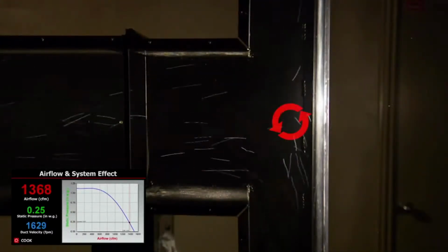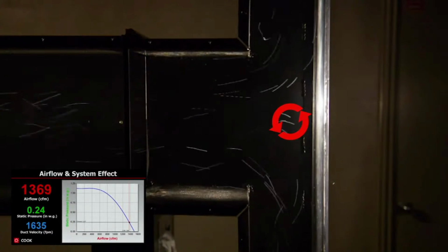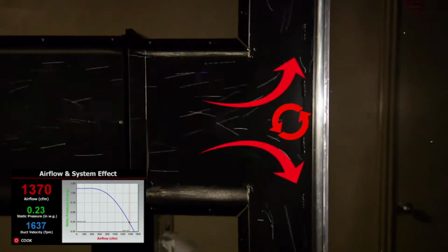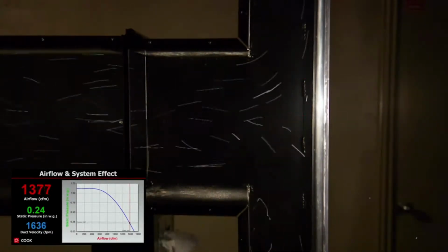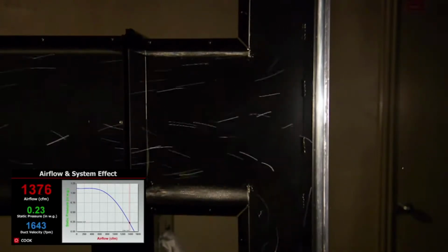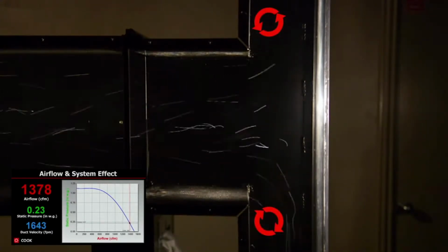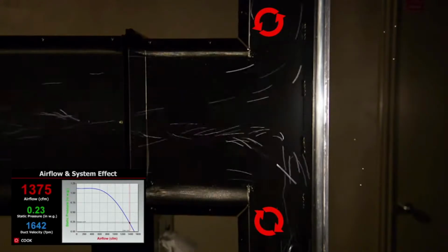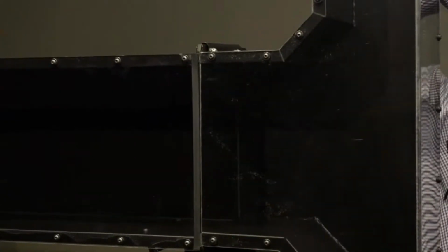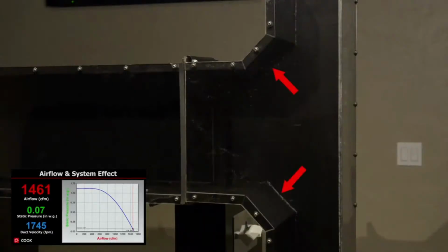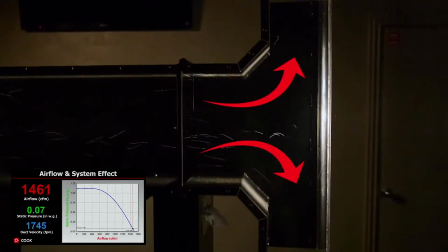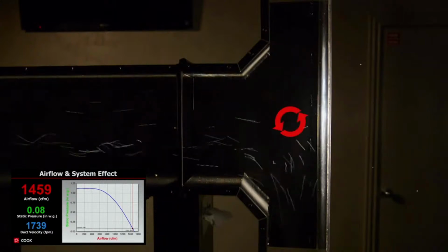Looking closer, we find that a small dam of air formed where the airflow splits, guiding the air to each branch. As we saw with the square elbow before, we are getting turbulence after the turn, contributing to the loss. Next, we have taken the bullhead T and mitered the throat of the fitting. This opens up the throat area, providing more room for a smooth flow in each direction and minimizing the turbulence downstream. The pressure drop is similar to the square elbow with turning vanes or short radius elbow.